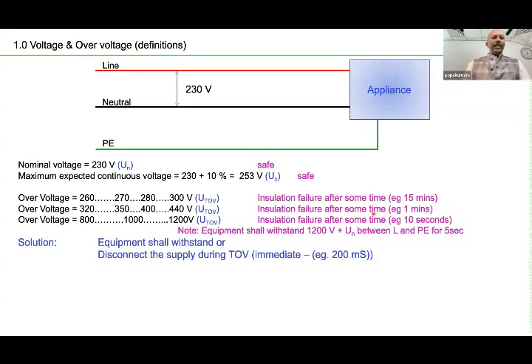So under these conditions, the equipment, under the conditions mentioned here in the list, may be able to withstand, depending upon its construction. Or if the equipment cannot withstand, the installer has to disconnect the supply. Something should trip. There shall be an over voltage relay and the relay should trip.